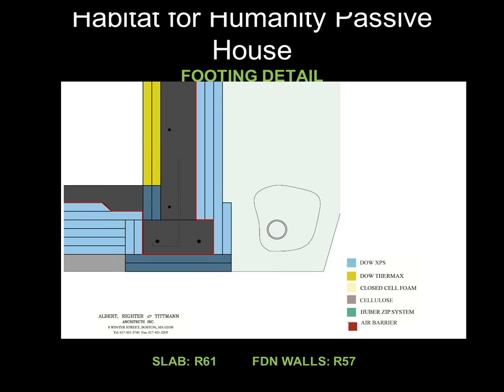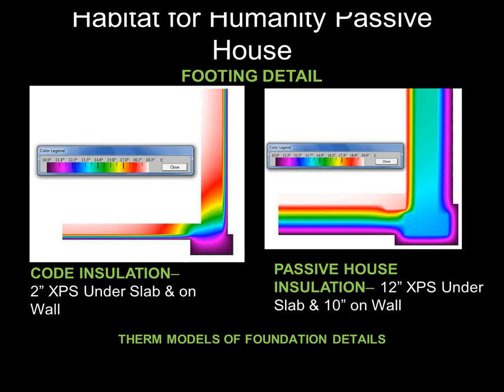Starting at the footing, the building sits on 4 inches of high-load extruded polystyrene. The slab itself sits on 12 inches of extruded polystyrene. There's about 6 inches on the exterior and 4 inches of Thermax on the interior. So we have a highly insulated foundation system completely isolating the footing from the ground. And you can see that here modeled in a program called Therm, which, again, I had mentioned, thermal bridging as being a really critical component to Passive House design, thermal bridge free design. Using the Therm program, one can analyze whether or not you have a thermal bridge, and you can also see the difference here between a code footing and our Passive House footing.